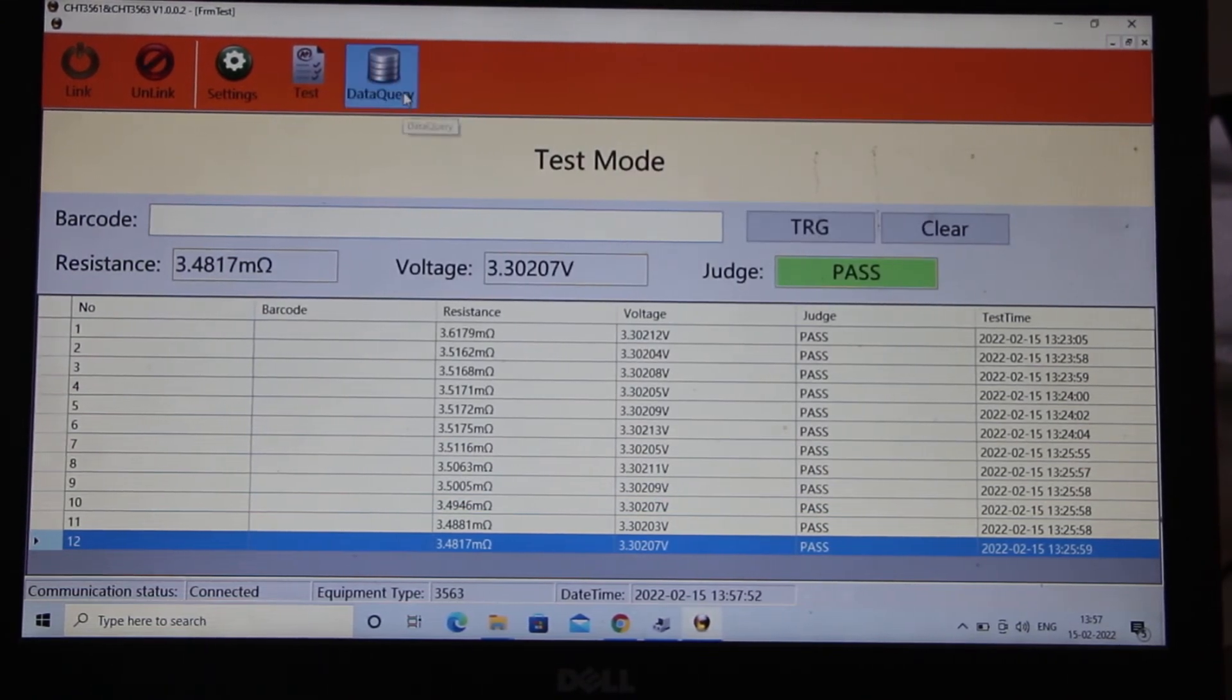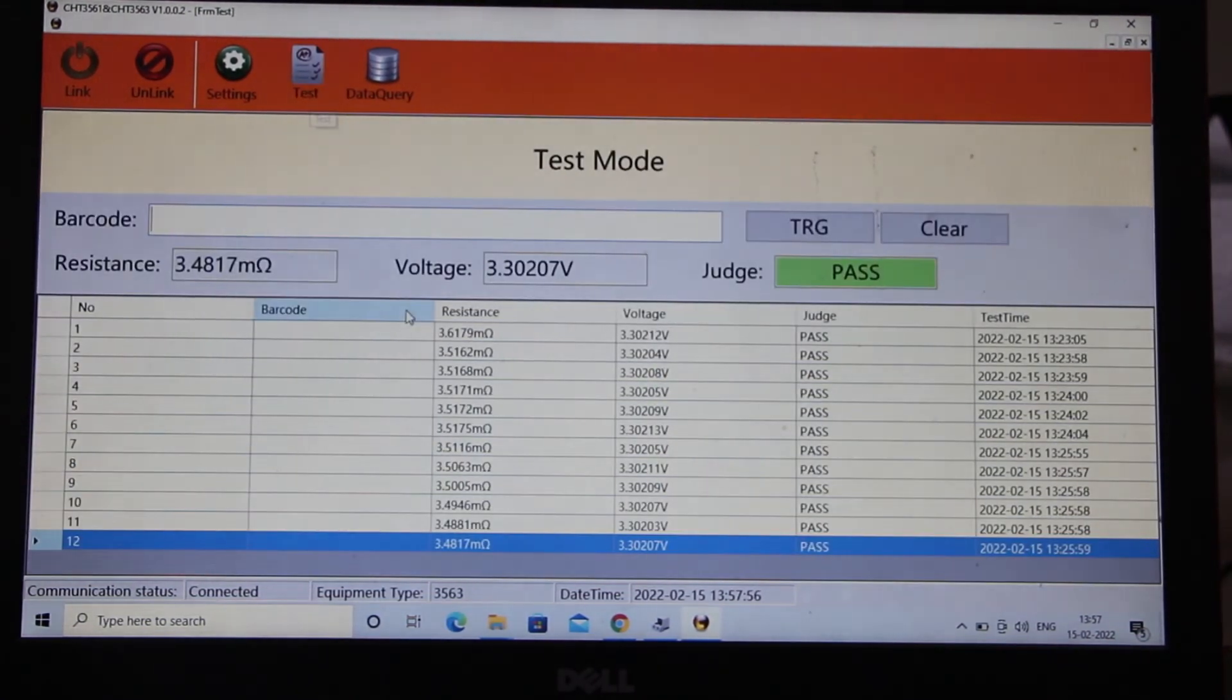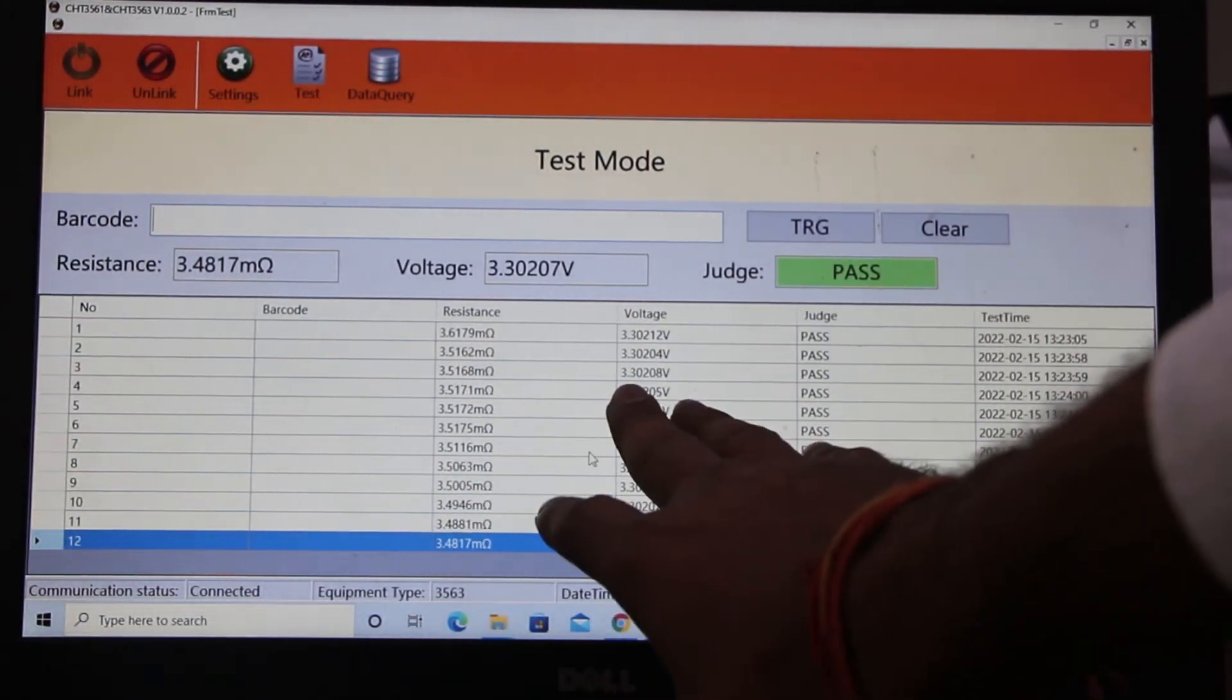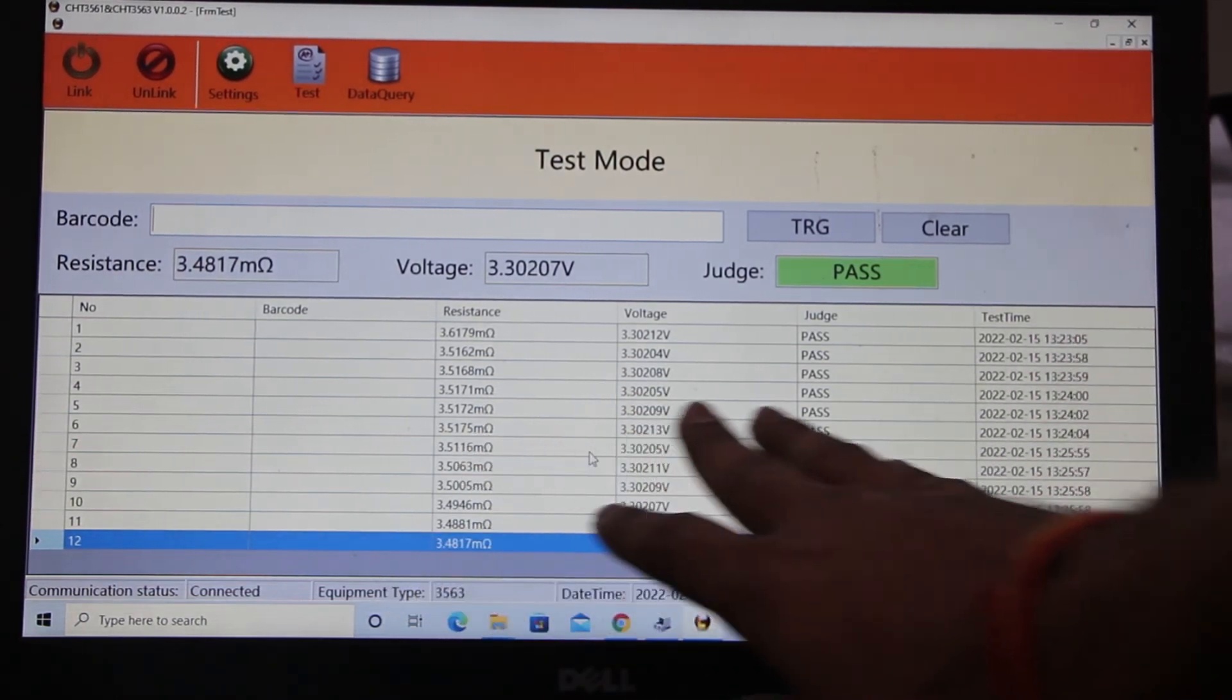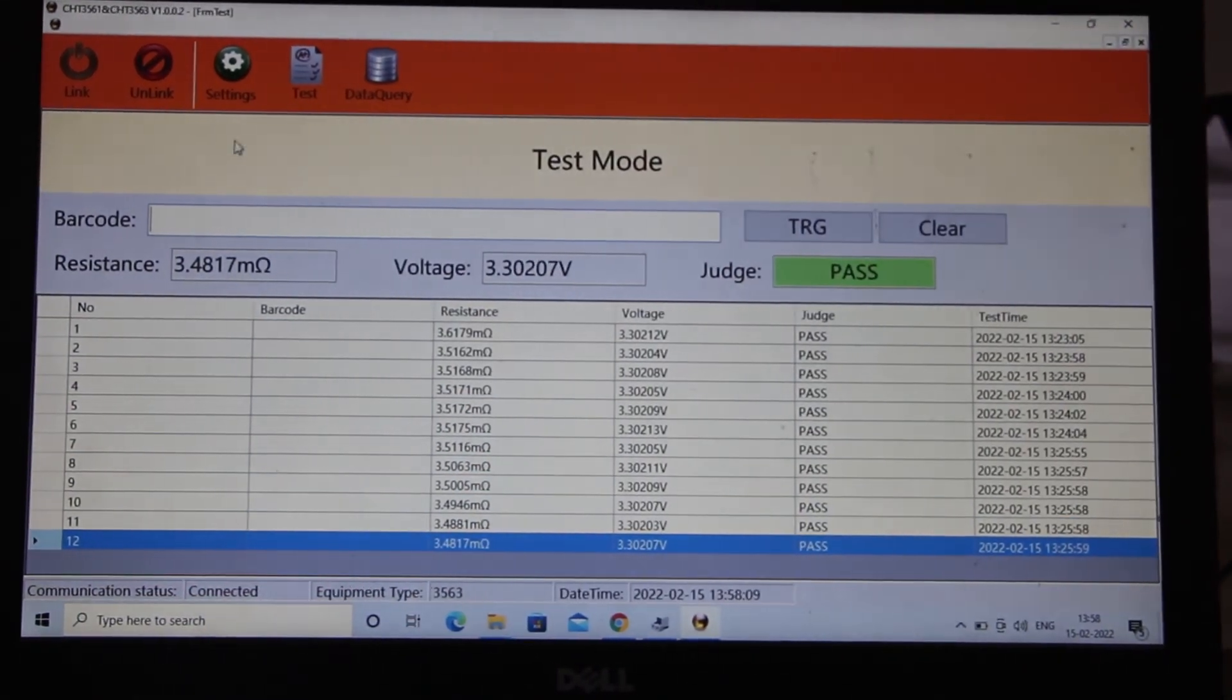Query data means you can get data from there testing means you can get your testing result from there as you can see that we have tested lots of times and each and every time we are getting some resistance and voltage according to your management purpose and the pass means it is within the range because in setting we put the range.